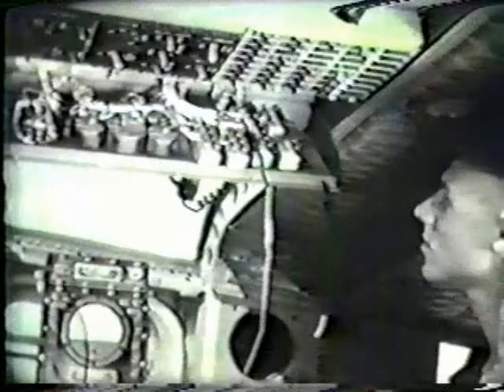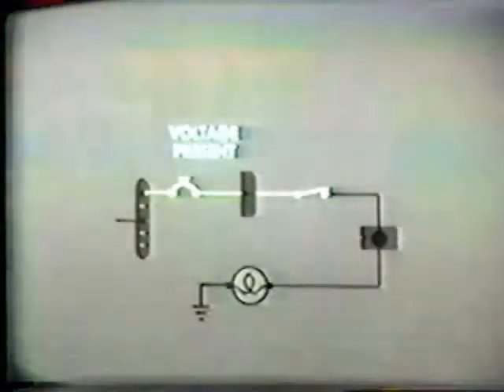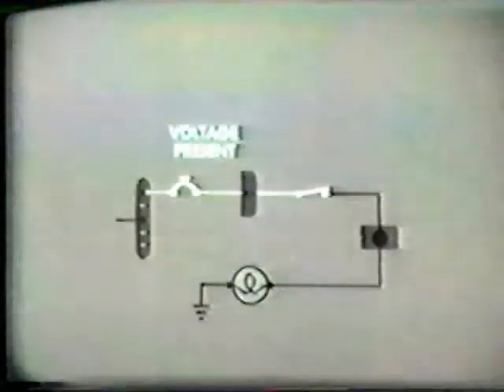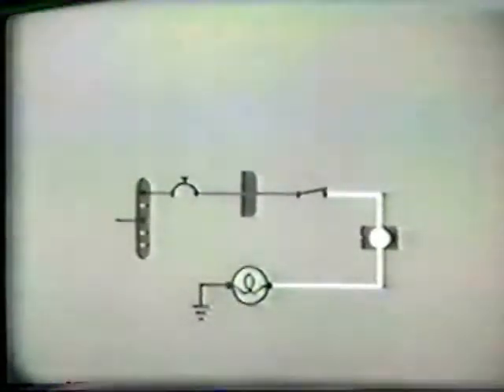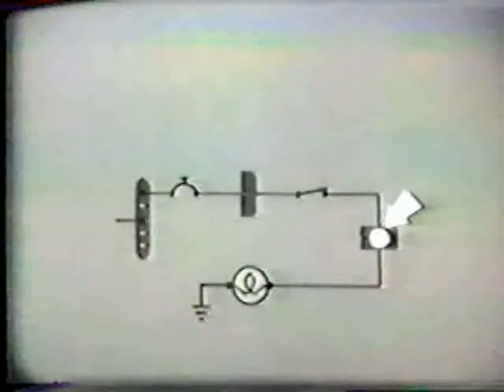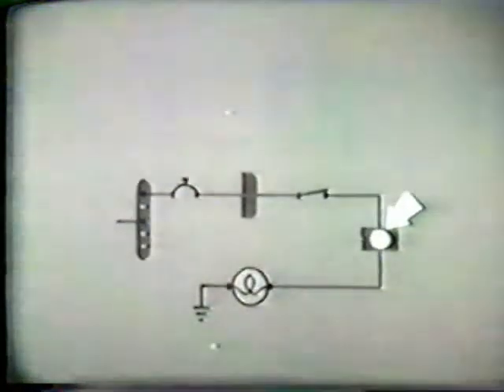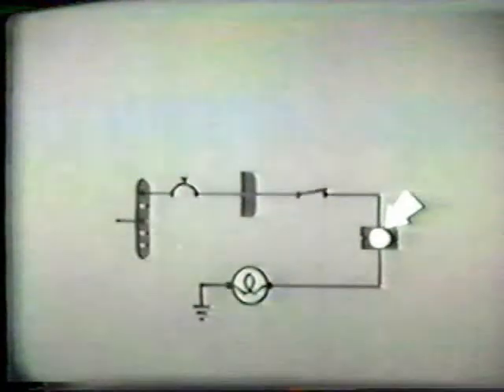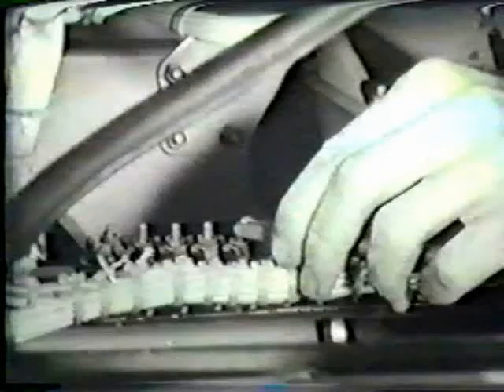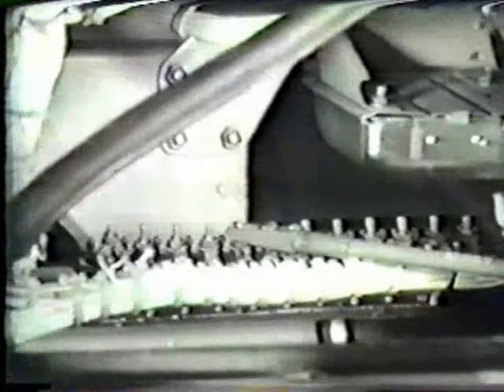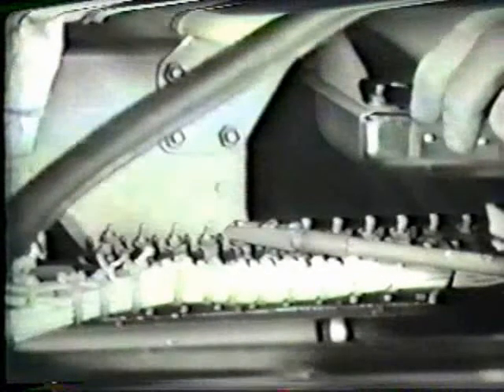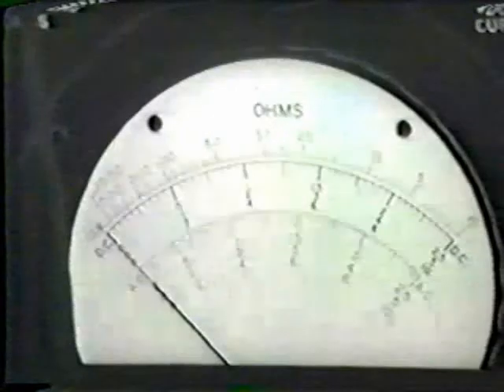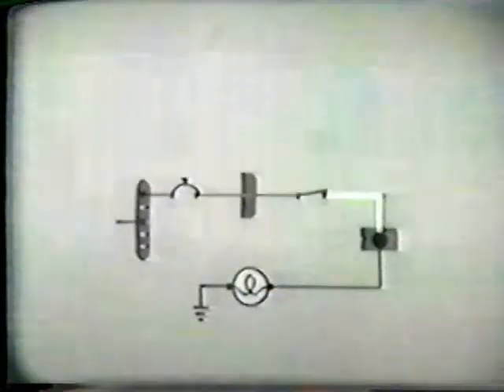We continue systematically with voltage checks and find that voltage is present up to the load side of the switch. This means that the open must be in one of the two segments of wire between the switch and the socket. A test at this terminal will determine which of the two segments of the wire is open. With the switch closed, a voltage check is made at the end of the first segment of wire. The scale shows no voltage. This proves that this first section of wire is open and our trouble has been found.